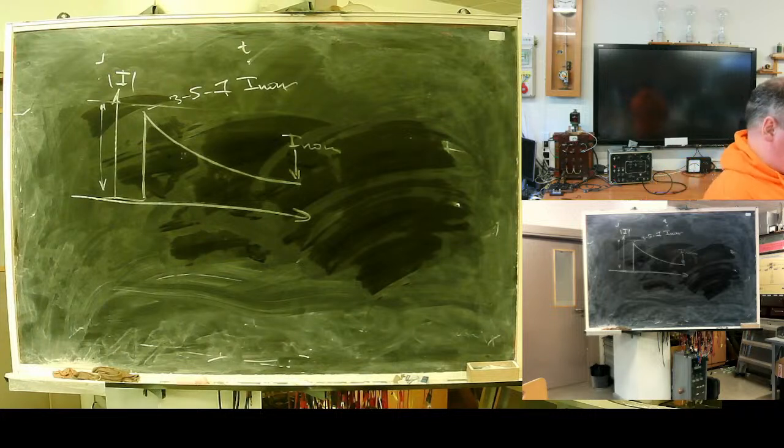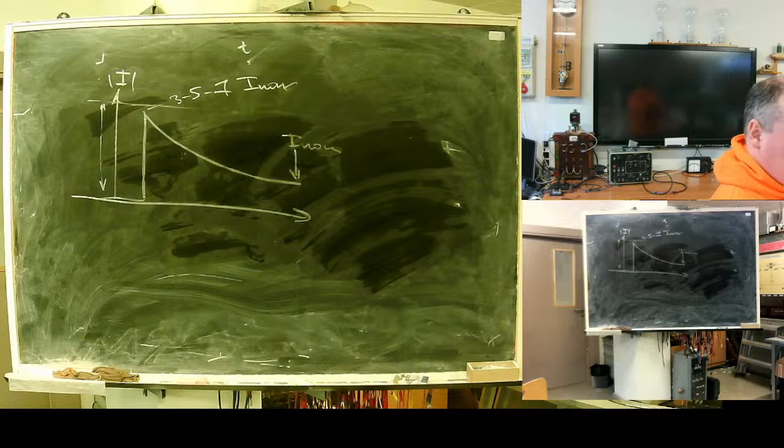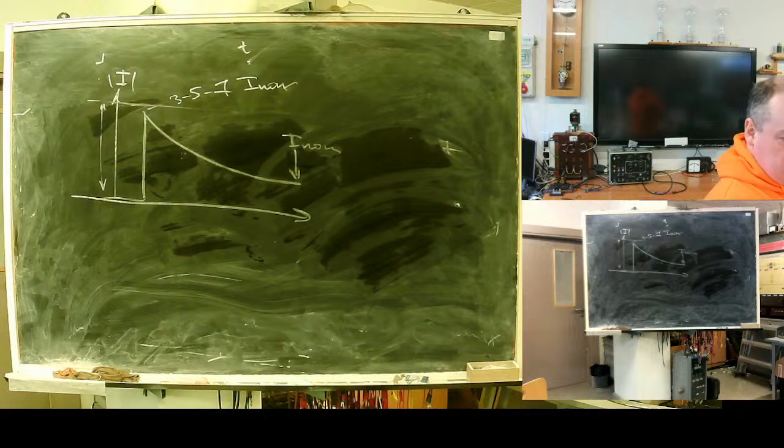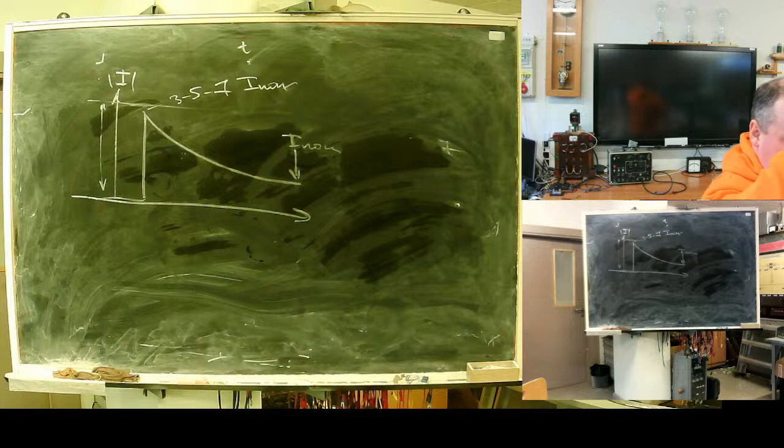If this one is marked group B, what's the instant current of group B? Here, B. Yeah, starting from 3 to 5. If it's rated 10 amps, group B, this means it should trip instantly from 30 to 50 amps.